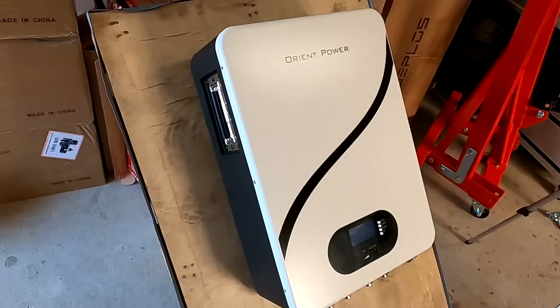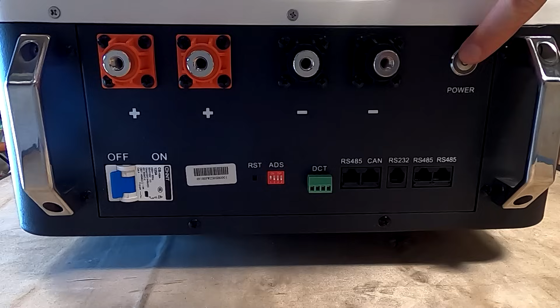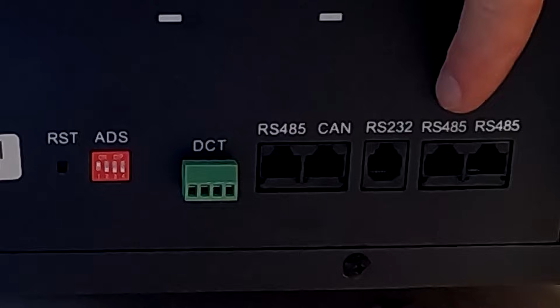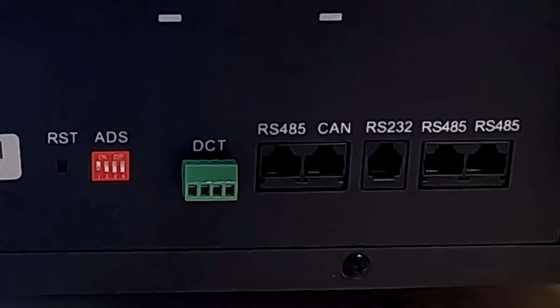The Jakiper Powerwall has a white lid and a black wave design, so it looks really nice when it hangs on the wall. The underside of the Jaki Powerwall comes with a power button, 2 negative and 2 positive M8 terminals, a 125 amp DC circuit breaker, a reset button, an ADS switch for paralleling these batteries, 2 dry contact terminals, and the usual communication ports - RS485 and CAN for inverter communication, RS232 for computer communication, and 2 more RS485 ports for paralleling these batteries.